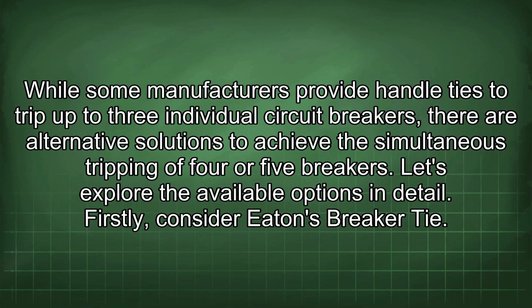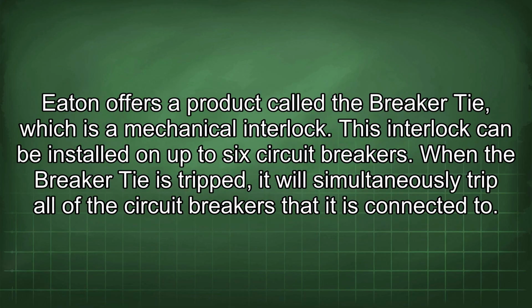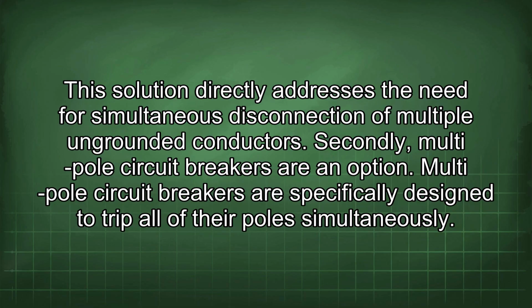Firstly, consider Eaton's breaker tie. Eaton offers a product called the breaker tie, which is a mechanical interlock. This interlock can be installed on up to 6 circuit breakers. When the breaker tie is tripped, it will simultaneously trip all of the circuit breakers that it is connected to. This solution directly addresses the need for simultaneous disconnection of multiple ungrounded conductors.